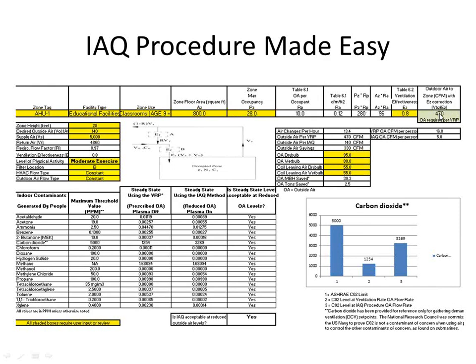You put in some things down here, basically your desired outside air, and this keys off of 5 CFM per person. It starts at that, although you can put in different ones. And the idea is to get yes here. If you get yeses here, you can use the IAQ procedure.